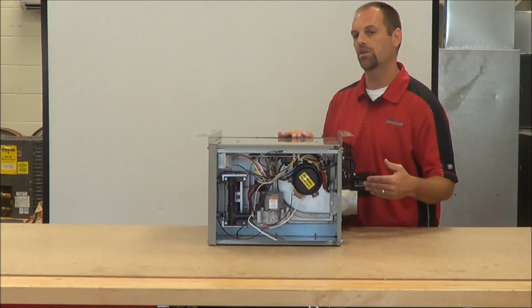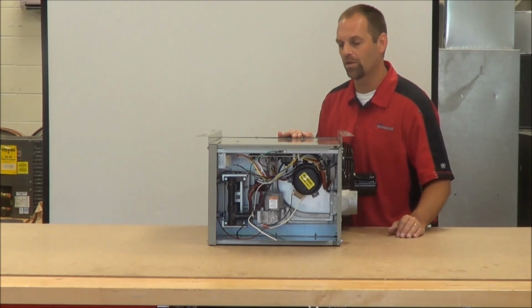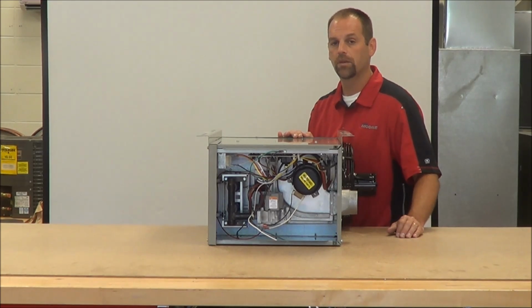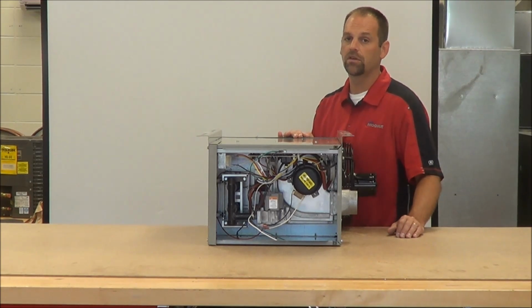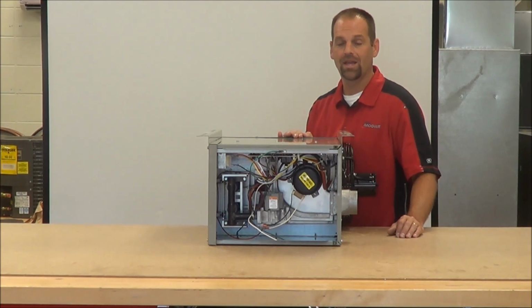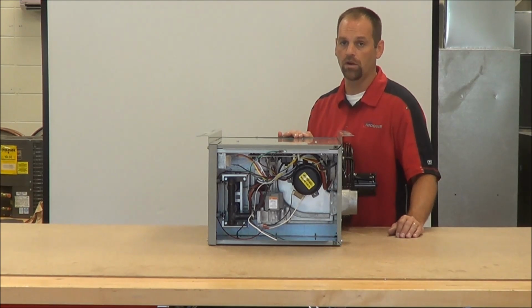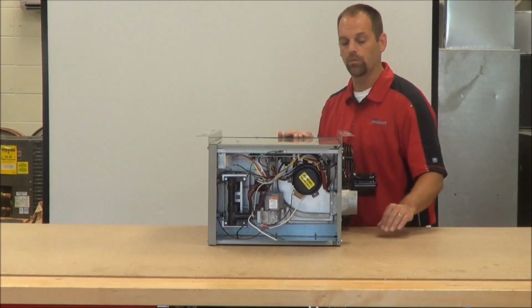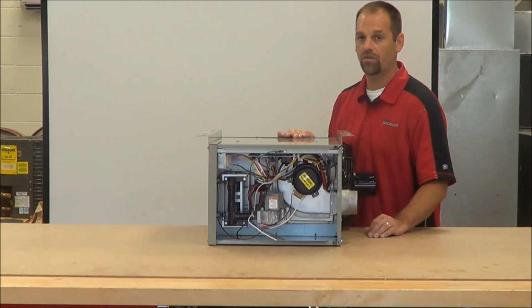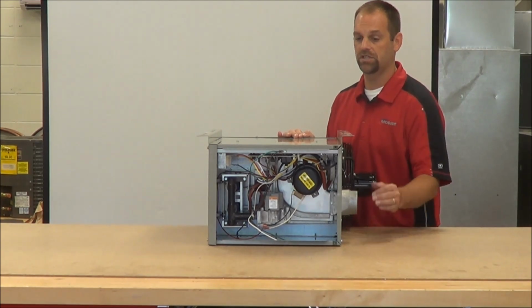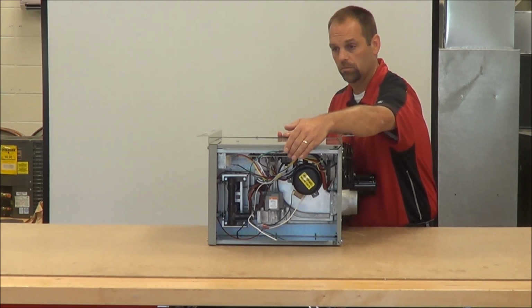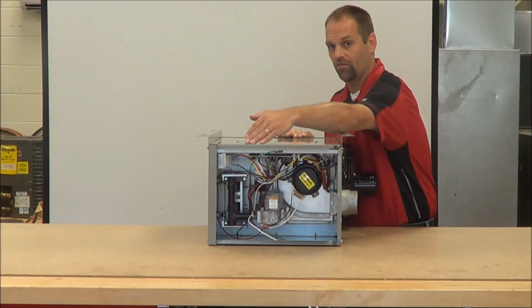So the first thing you want to do, look at your wires from your thermostat to the unit. If you think it's excessive, we probably need to change to a different gauge wire. If that's proper, you probably have a short in one of those wires. At that point, what I would do is I would remove your thermostat wires from the unit, so you disconnect it from the control board, replace the transformer.